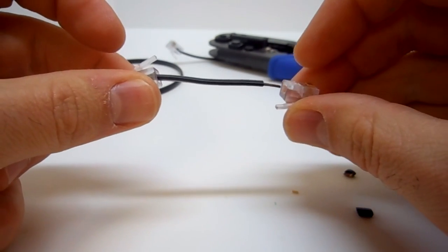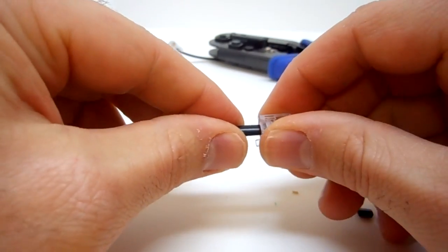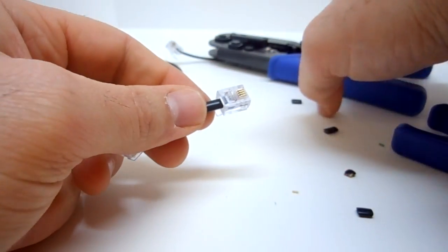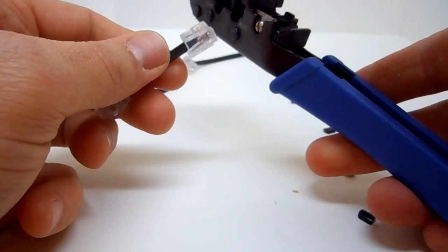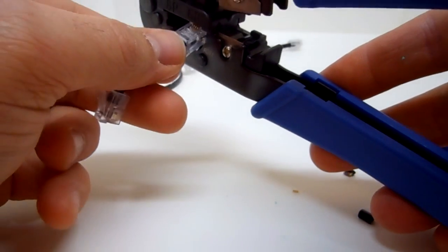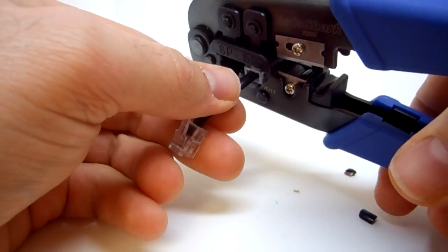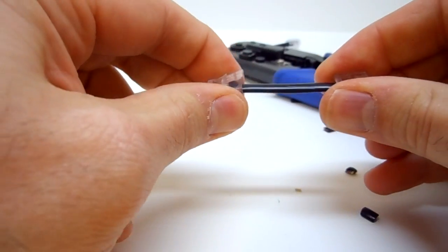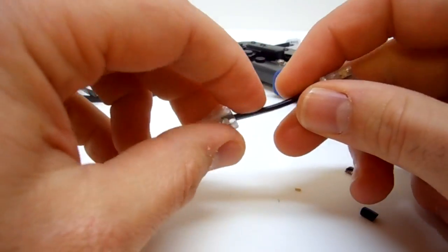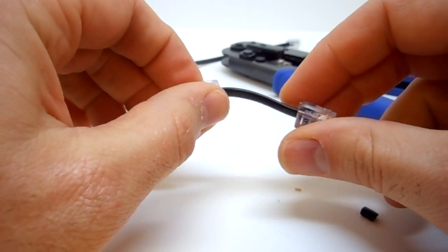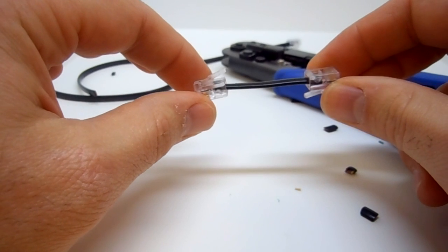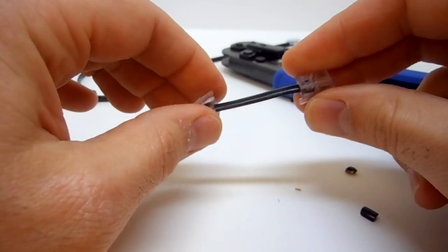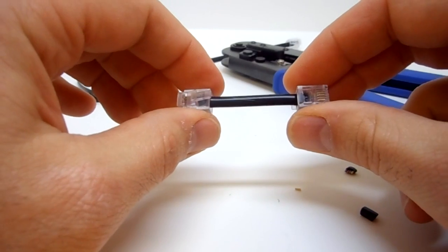We have our tab up on this connector, so we make sure the tab is down on this end. We insert it, make sure the conductors are all the way to the front of the connector, and then we insert our connector into our crimping tool again and squeeze. We remove the connector and give it a little pull test to make sure everything's good. You can also check it for continuity. If you stripped it correctly, made sure everything was 90 degrees, visually inspected each one and gave it a pull test, then you're probably good to go.